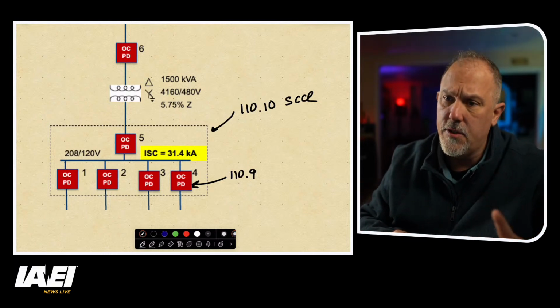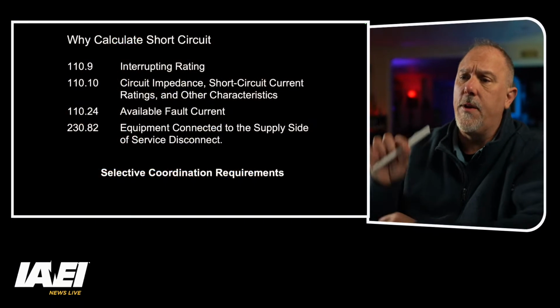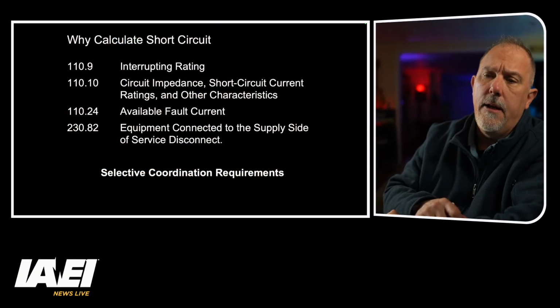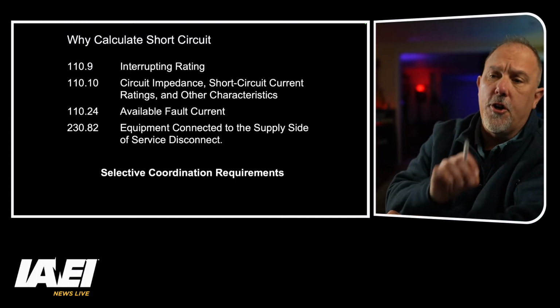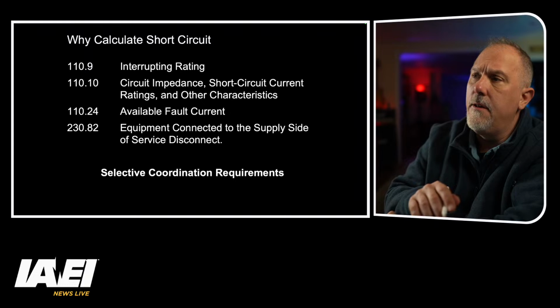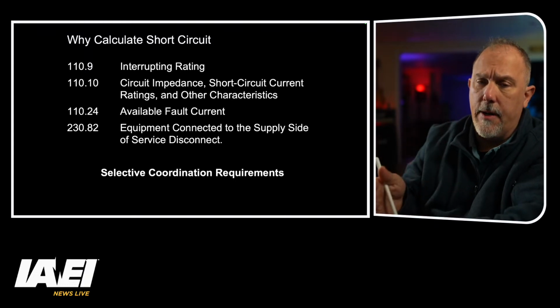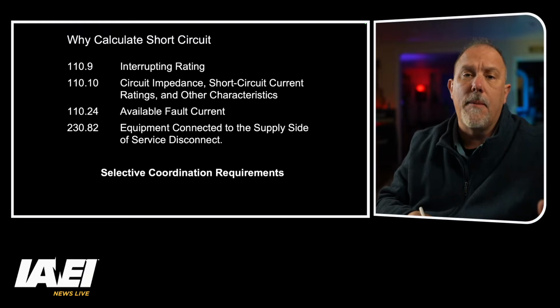Now remember, there's a difference between the interrupting rating and the short circuit current rating. 110.10 focuses on a short circuit current rating. 110.9 is an interrupting rating. Now the difference is that a short circuit current rating, as we said, is the ability of the equipment to let current pass through it and not achieve an unintended rapid disassembly in the field. You don't want that equipment to just come apart because of the magnetic forces.